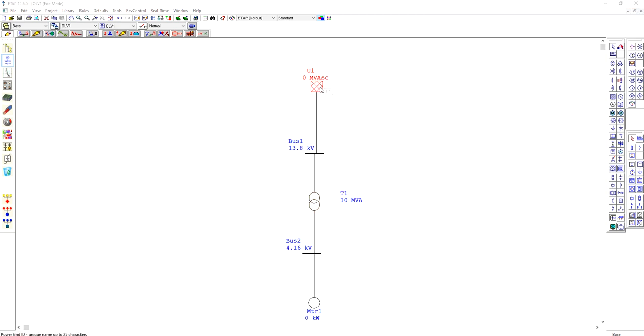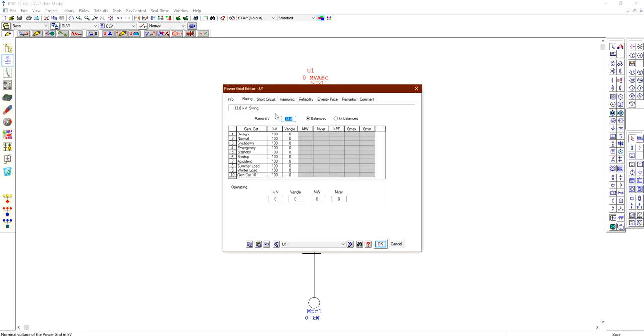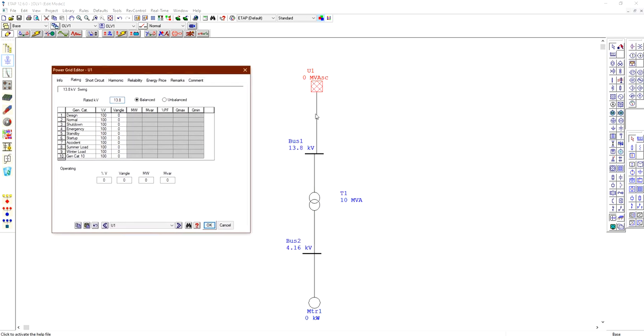Double-clicking the power grid opens its settings. You can choose from different operating modes: swing, voltage control, MVAR control, power factor control, and others. You can set the grid as in service or out of service. Under the rating tab, the rated kilovolt is 13.8, matching the primary bus voltage and the primary of the transformer. You can also choose a balanced or unbalanced grid.